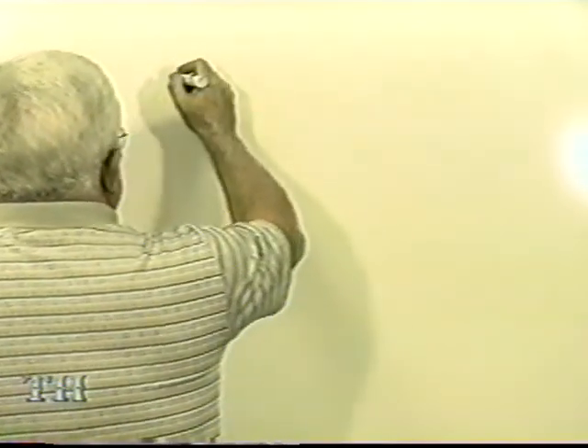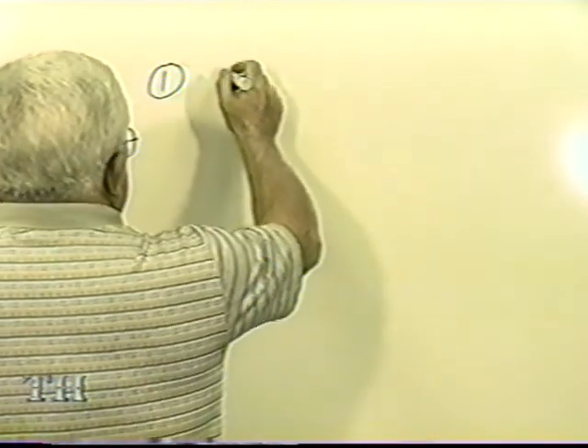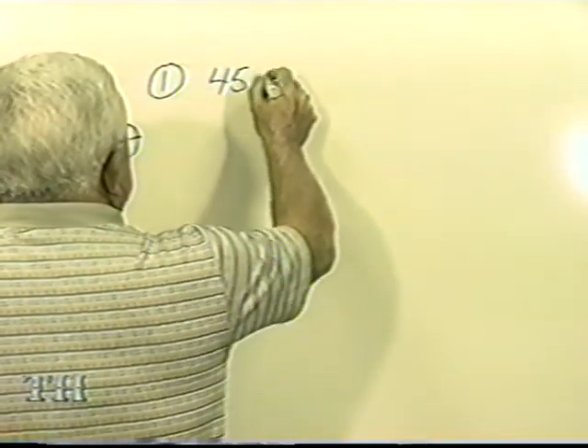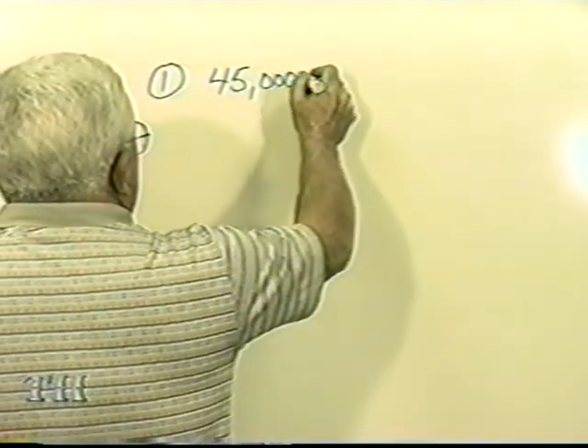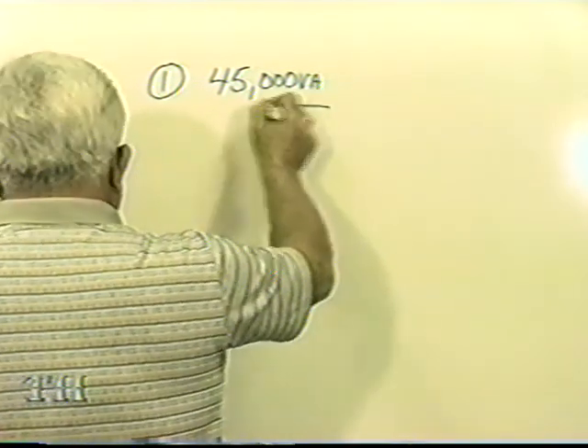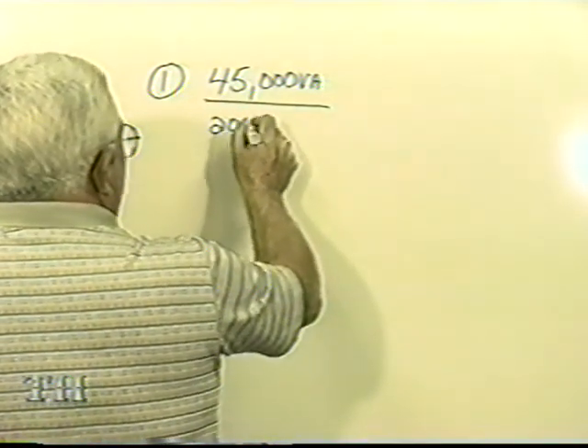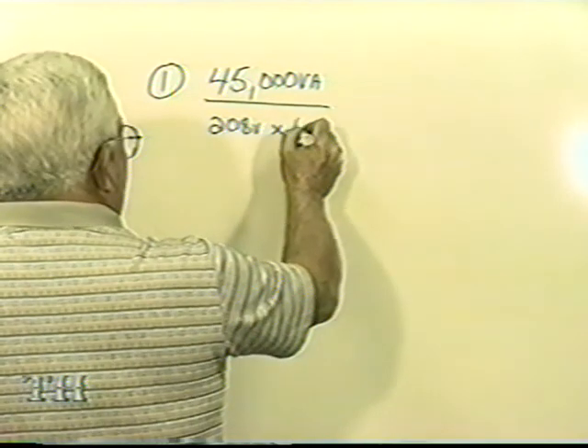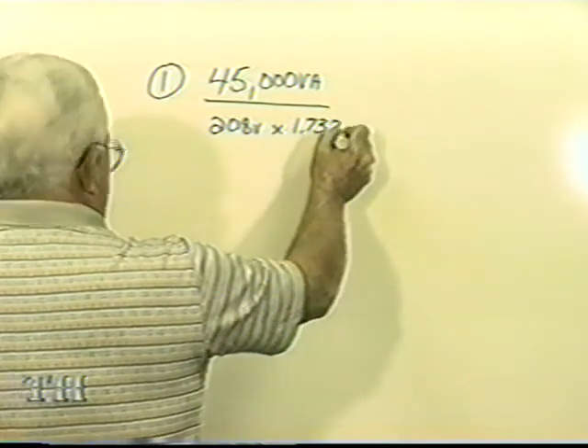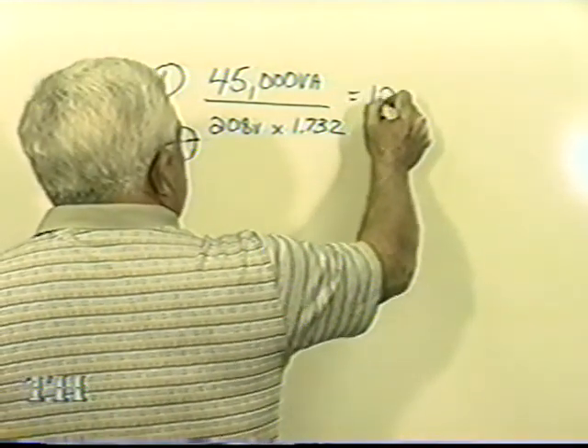Now on sheet 4, the answer to number 1 is D, 125 amps. That's the secondary line current. And what you would do in question 1 is take the 45,000 volt amp and divide that by the line voltage times the square root of 3. And you're looking at 124.9.